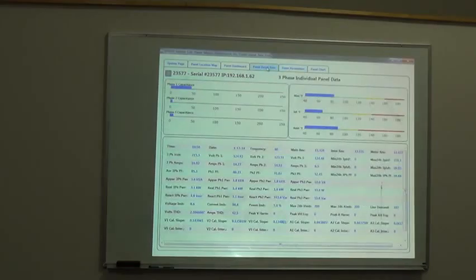Okay, so on the panel, let me see. Well, sometimes the numbers are so many digits and sometimes they're not. It requires me spending about 15 minutes on each one of them, rounding to a certain number. These numbers, the slope coefficient, the calibration coefficients, they really do need 5 digits, okay?